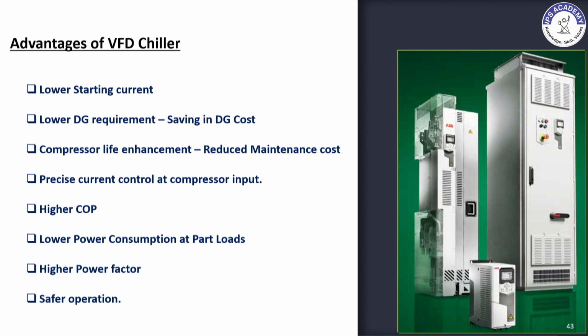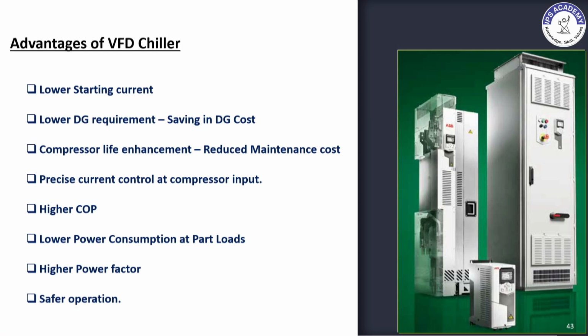What are the advantages of a VFD chiller? It lowers the starting current, lowers DG requirement, increases the compressor life, gives precise current control at compressor input, has higher COP, lower power consumption at part loads, and higher power factor, and is safer in operation.